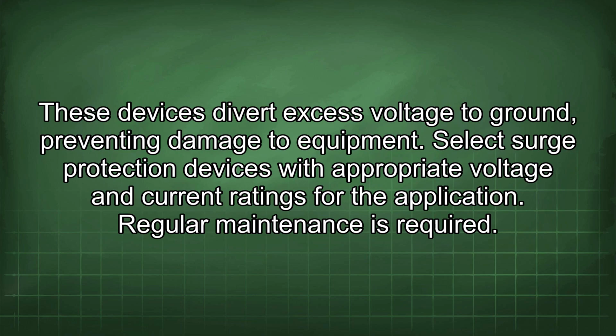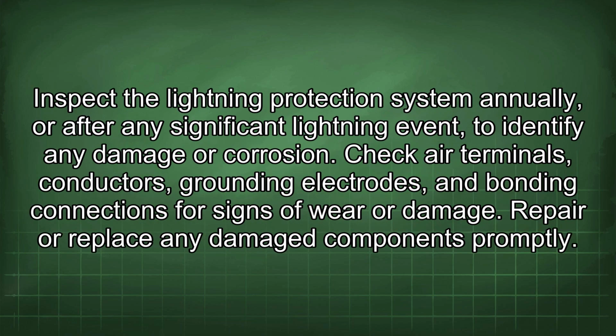These devices divert excess voltage to ground, preventing damage to equipment. Select surge protection devices with appropriate voltage and current ratings for the application. Regular maintenance is required. Inspect the lightning protection system annually or after any significant lightning event to identify any damage or corrosion. Check air terminals, conductors, grounding electrodes, and bonding connections for signs of wear or damage.